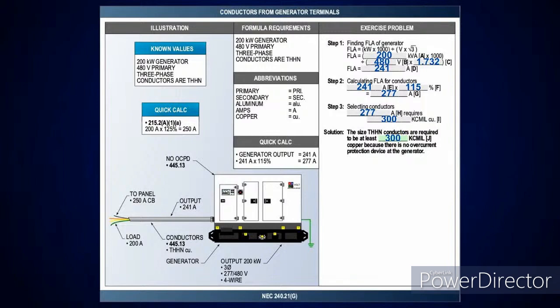But now I also have to take that at 115%. And people say, well, where do you get the 115%? Go over and look at 445.13. That's where you're going to get the information that I've got to put 115% on it. All we're doing is showing you in that illustration, how did I get that 241 amp output? Well, that's how I got it, by doing that calculation there. So take the 241 amps at 115%, it's going to give you 277 amps.